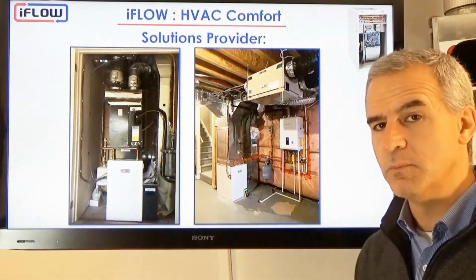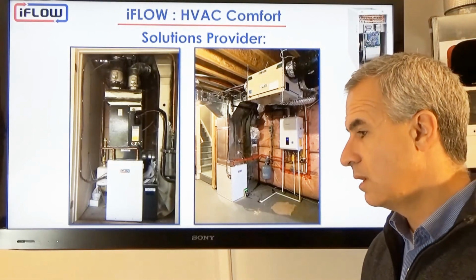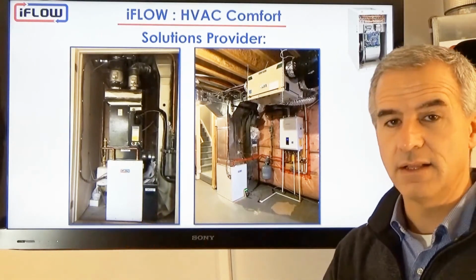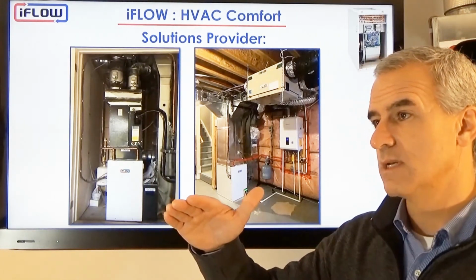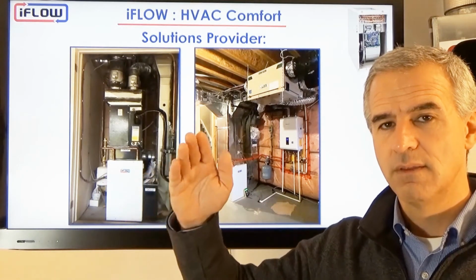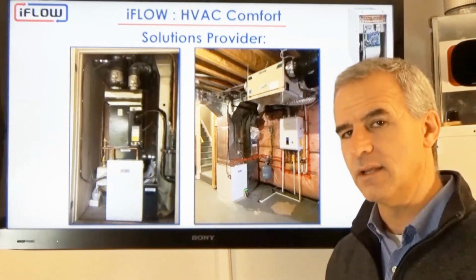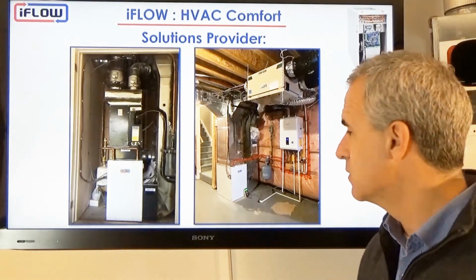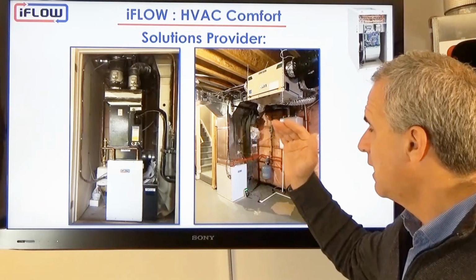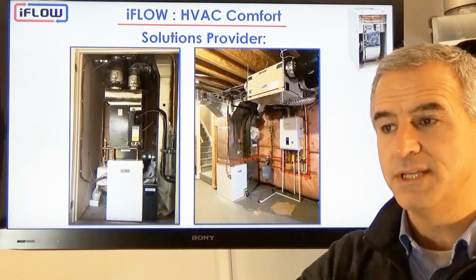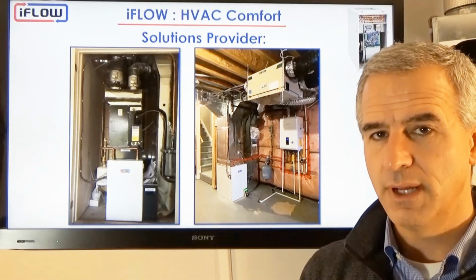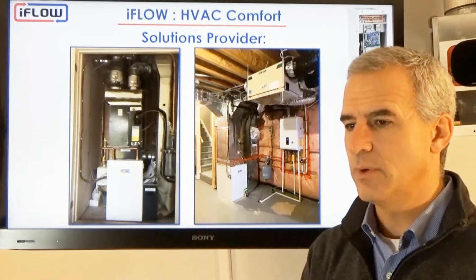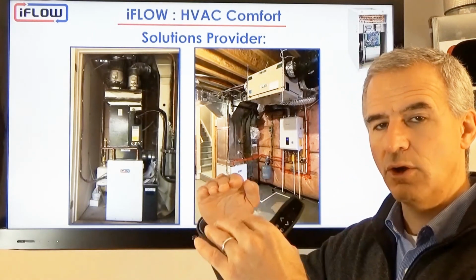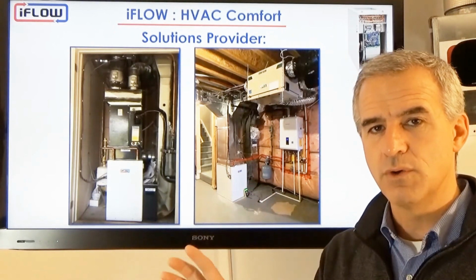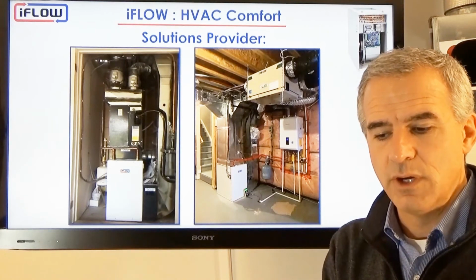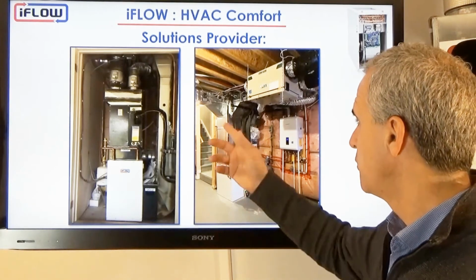Well, if my minimum input on my furnace or on my tankless water heater, for example, is above that 10,000 BTUs, then it's going to be cycling a little bit. We'll look at cycling in some other videos. But if we can match the BTU load in the home to the appliance, then it's a perfect pairing. So we want to make sure we have the maximum heat load met, but then the minimum heat load. And when we're zoning, those minimum heat loads are going to be divided into 3 or 4, depending on the number of zones.